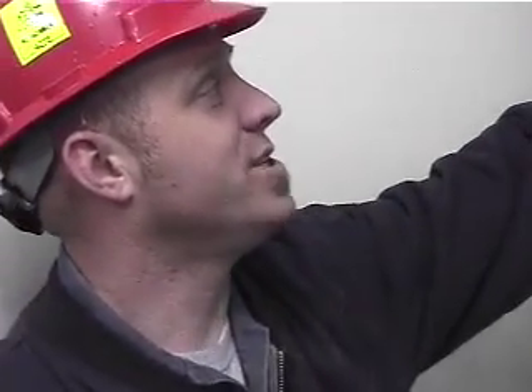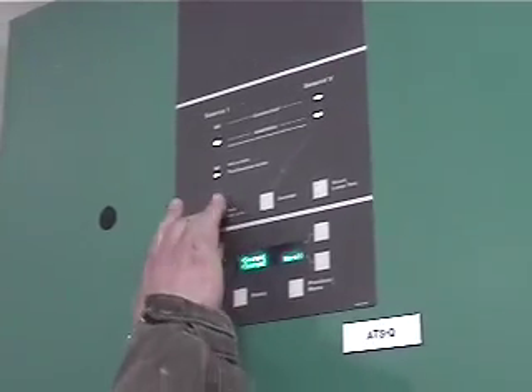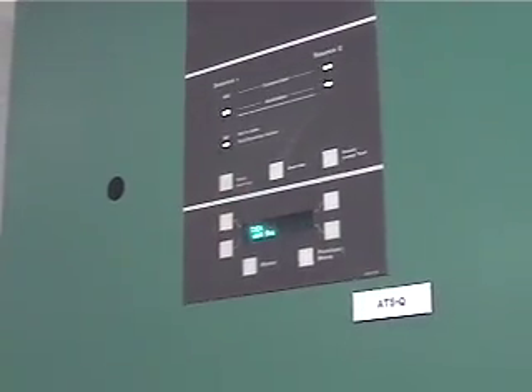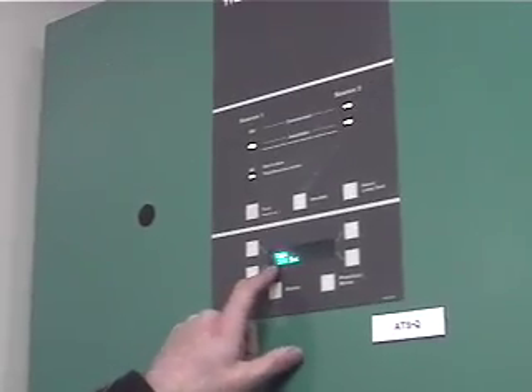Now, once you're in test mode, if you leave it, it's going to run forever, so you have to stop a test. If you ever do this, you're supposed to do it for half an hour, let it run for 20 minutes, then come back and push that button a second time. So to complete a test, just push that button and let off. The test light will flash saying, hey, I got the signal. Yeah, that's good.